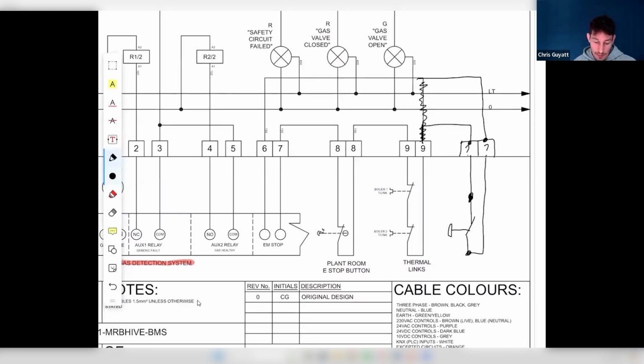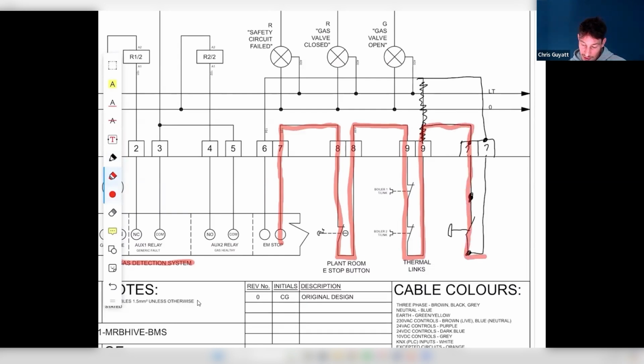That's it. So now let's just quickly go through that circuit again. We're coming out of the gas detection system into the panel, out of the panel to our first e-stop, back in the panel, out to our thermal links above the boiler, back in the panel, and then out to our new e-stop in the reception area, back into the panel, and then back to the gas detection system. Simple as that, guys. Everyone happy with that? Does that make sense? Yeah.